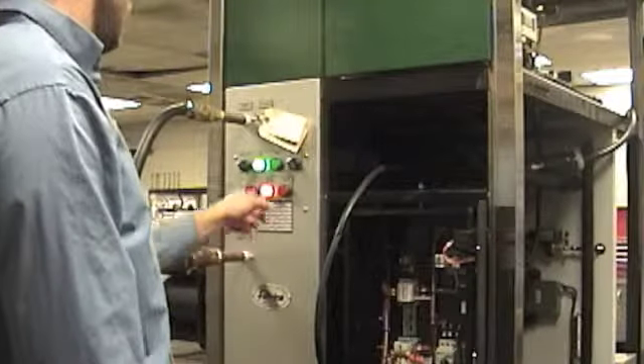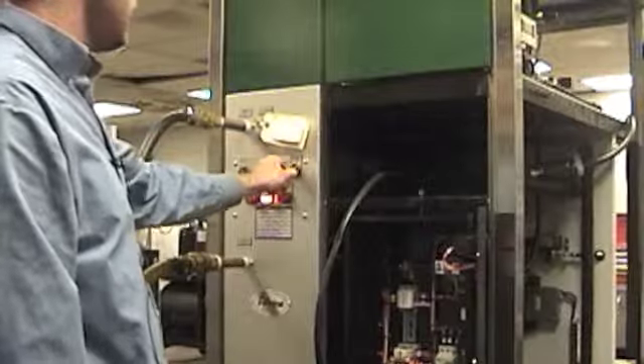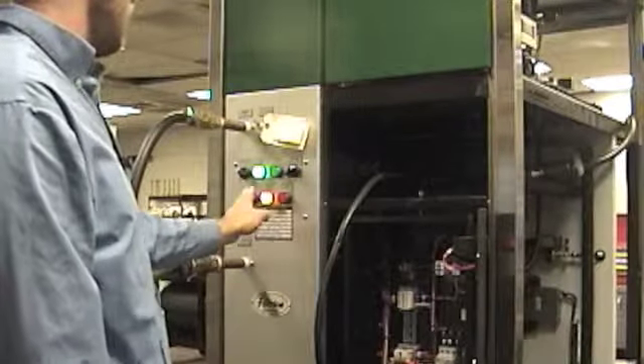So after the unit's running, you can turn on the sterilizer, and you're going to want to make sure that the light goes off. In this case, it did not, so that would indicate that the sterilizer board needs to be calibrated. The sterilizer board is right in the electrical box. You shouldn't have to adjust it. We adjust it in the factory. However, if you need to, its location is right here, the adjustment screw. And this will adjust the sensitivity of the sensor, the UV sensor.